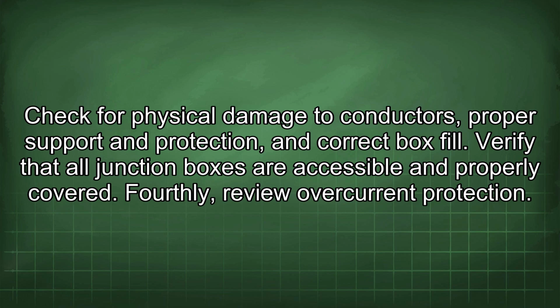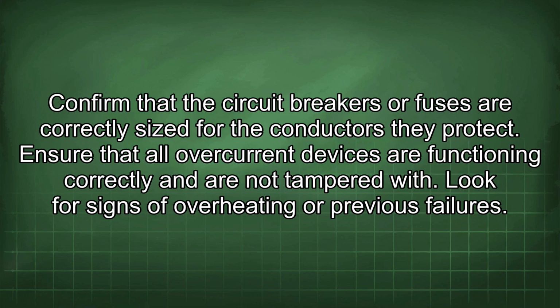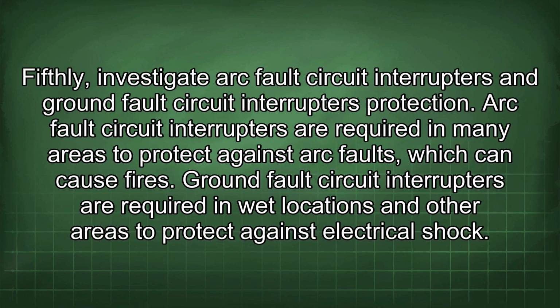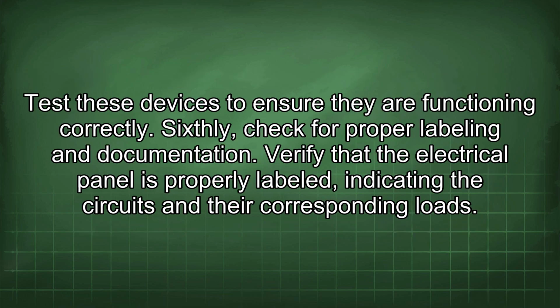Fourthly, review overcurrent protection. Confirm that the circuit breakers or fuses are correctly sized for the conductors they protect. Ensure that all overcurrent devices are functioning correctly and are not tampered with. Look for signs of overheating or previous failures. Fifthly, investigate arc fault circuit interrupters and ground fault circuit interrupters protection. Arc fault circuit interrupters are required in many areas to protect against arc faults, which can cause fires. Ground fault circuit interrupters are required in wet locations and other areas to protect against electrical shock. Test these devices to ensure they are functioning correctly.